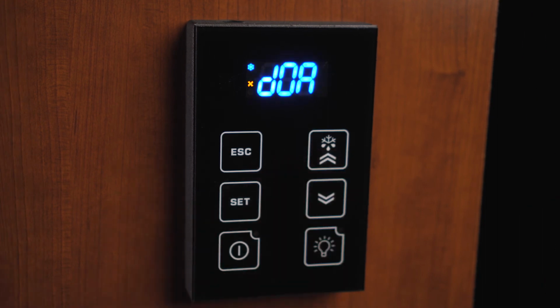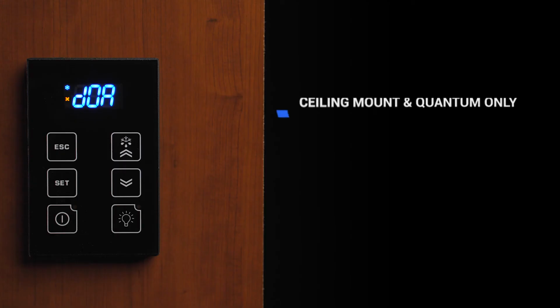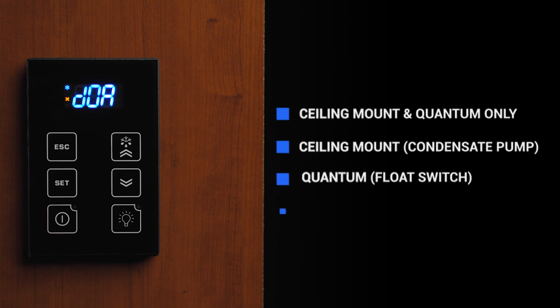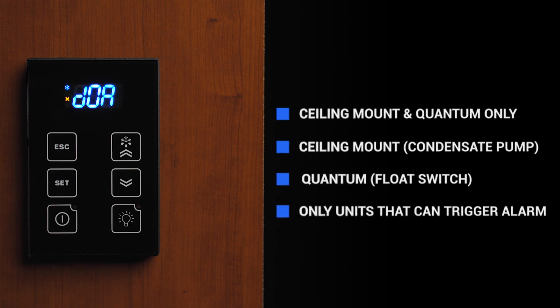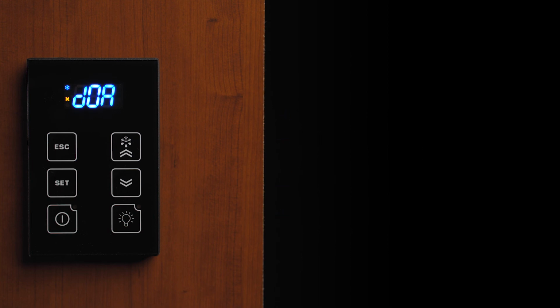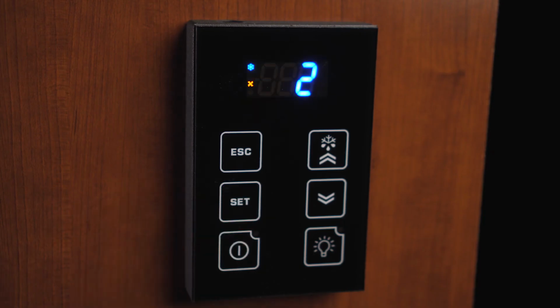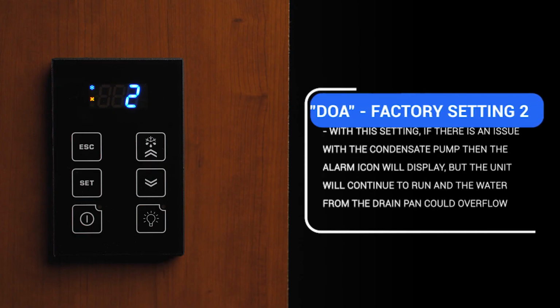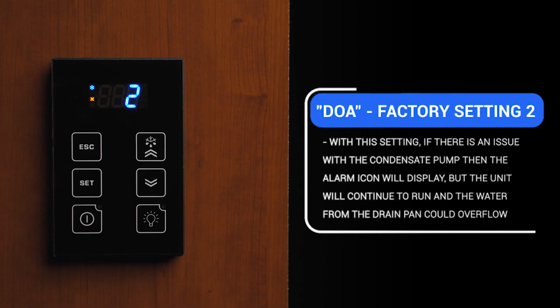DOA is a setting that only applies to our ceiling mount and quantum units. These are the only units that use a condensate pump or float switch that would trigger an alarm. It is factory set at 2, which means if there is an issue with the condensate pump, the unit will show the alarm icon on the display. The unit will continue to run, which will allow the unit to keep cooling your cellar, but since there is an issue with the pump, the water in the drain pan could overflow into the cellar.